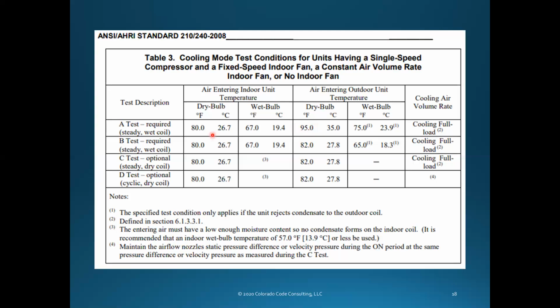So what are you guys designing for? Is everybody comfortable at 80 degrees inside their home? Is that where you set your thermostat? Remember last week we said it's actually 75 degrees. This is why it's important never to just look at the AHRI data—it's because it's not what the design is. We're never designing to 80, so instantly this is all wrong for everybody. It's only good to make sure we're comparing equipment correctly.